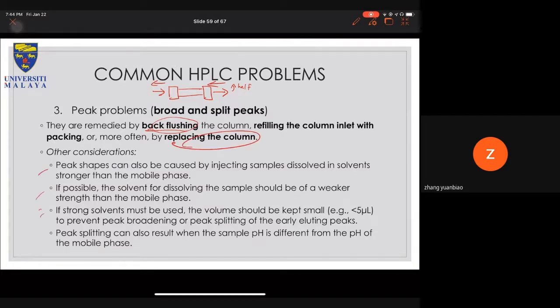So another consideration, if you do see a broad or a split peak: peak shape can be caused by injecting sample dissolved in solvents stronger than the mobile phase. As I mentioned at the very beginning of the lecture, sometimes you dissolve the sample in methanol, but when you run your system, you use acetonitrile and water. So you might see this happen. If possible, the solvent for dissolving the sample should be of a weaker strength than the mobile phase. If a strong solvent must be used, the volume should be kept small. For example, if you have issues with the sample dissolving in acetonitrile or water, you might try to use DMSO, dimethyl sulfoxide, which is a very strong solvating agent.